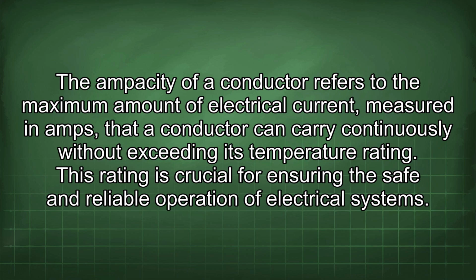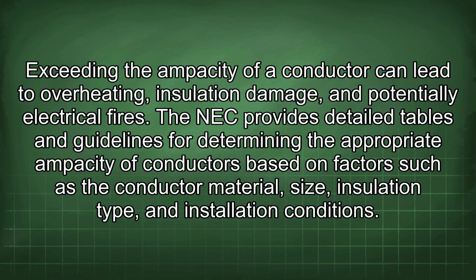The ampacity of a conductor refers to the maximum amount of electrical current, measured in amps, that a conductor can carry continuously without exceeding its temperature rating. This rating is crucial for ensuring the safe and reliable operation of electrical systems. Exceeding the ampacity of a conductor can lead to overheating, insulation damage, and potentially electrical fires.